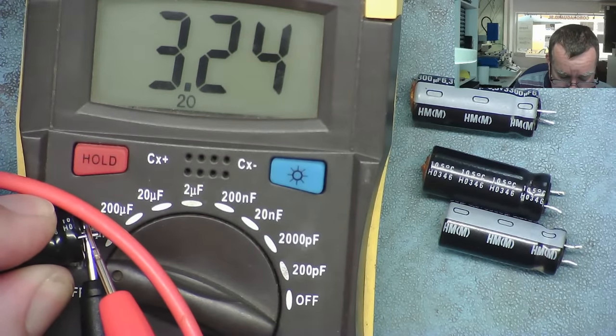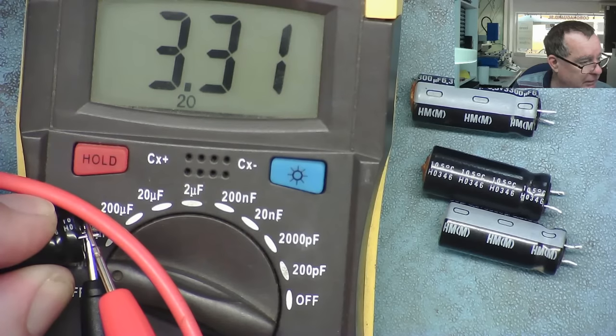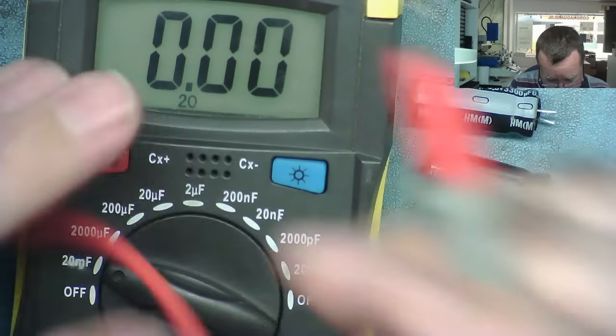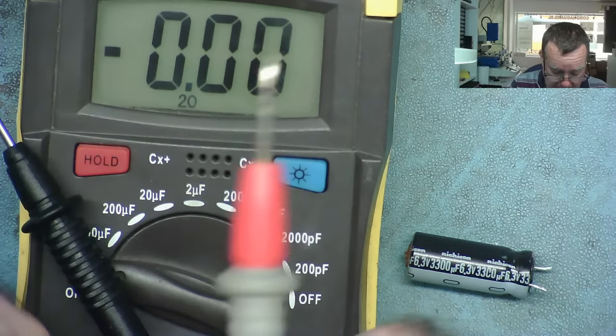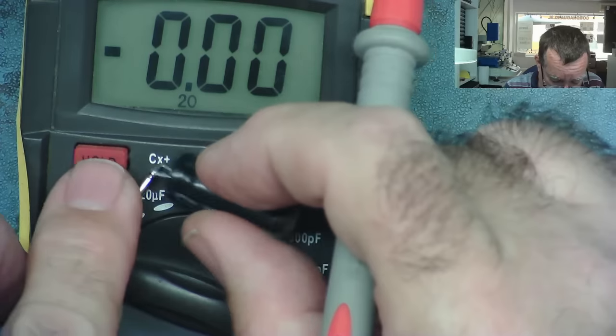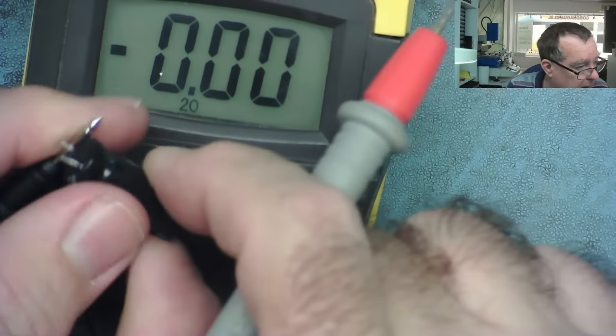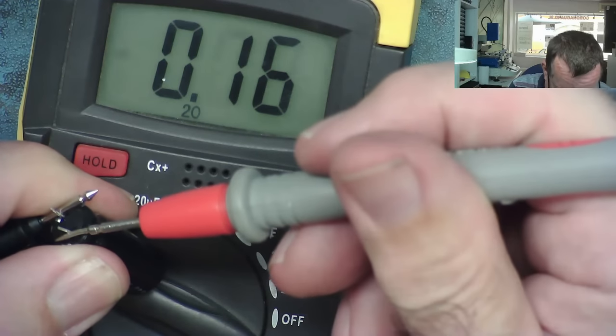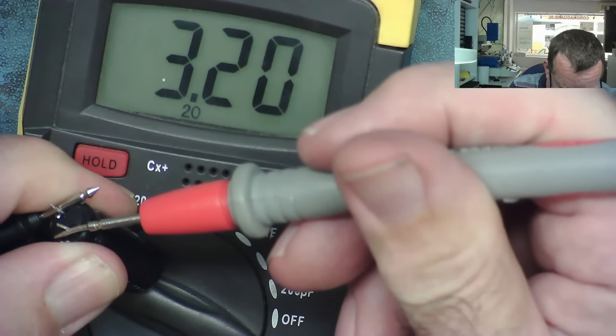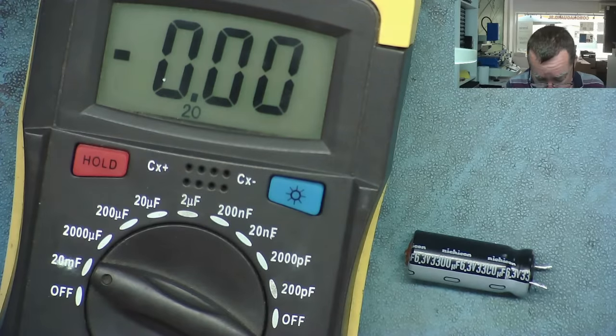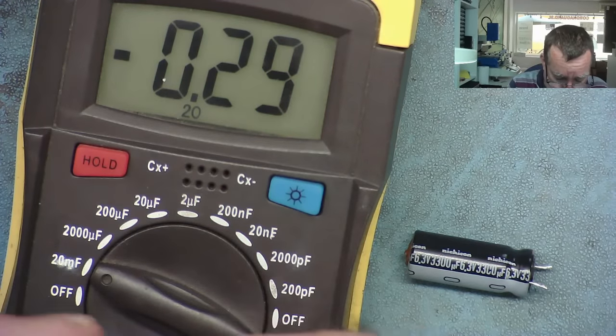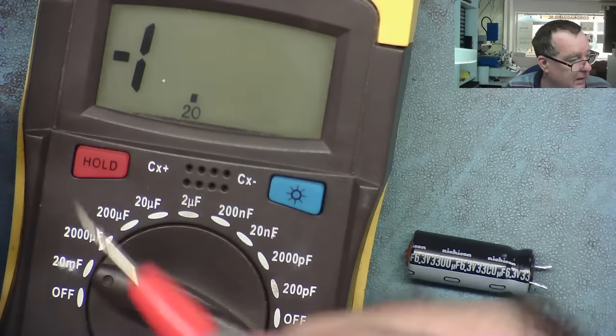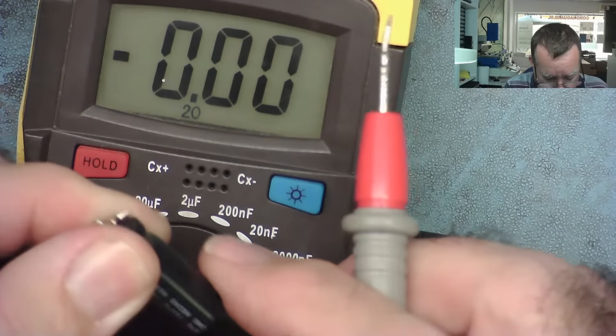That's reading about correct, yeah, 3,300 - as bad as it looks, that actually reads 3,300. We can visibly see it's bad, but it's reading okay. Here's another one - how's this one reading? That reads about okay again. This is a little unusual - quite often capacitors with this type of damage... this one's just bulged, slightly better than the other ones.